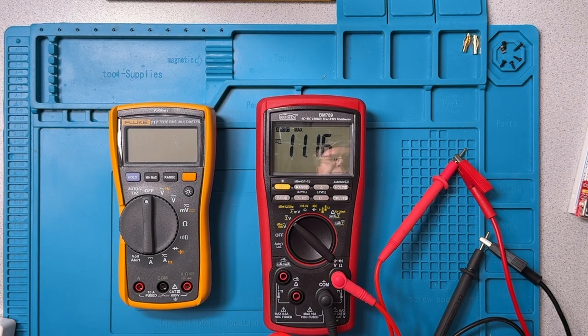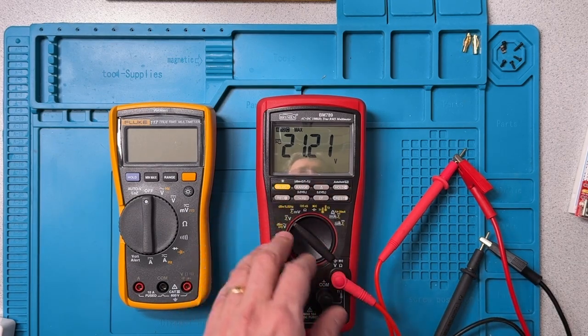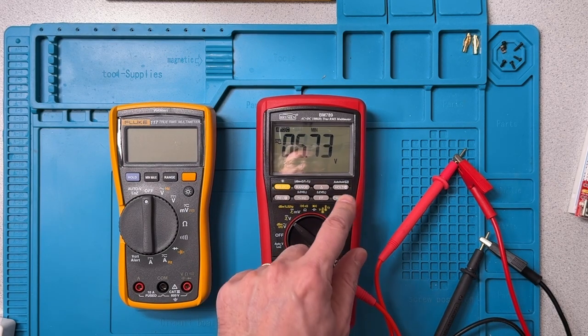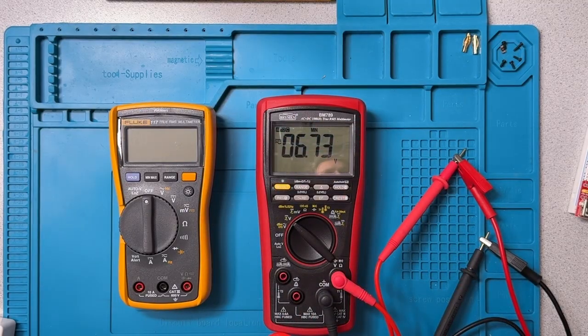So it shows the maximum. Now I'm changing the voltage, but it's below the maximum, and so it's not going to lock in a new value of max. But if I go up here higher, I'm now changing it around 20 volts. If I stabilize for a second, then it picks up that new maximum. Now I've gone below, and so that stays locked in. And so Crest is kind of like auto hold, but for a max or for a min. Okay, so there's a min. You can see it had a minimum that it hit while we were doing all of that as well.